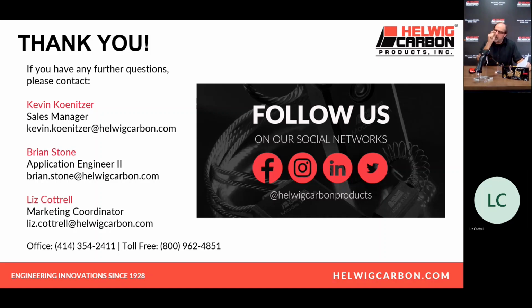Projected life. Even our smallest little kits for little motors that are tucked inside there, we're still talking minimum 5 years under 24/7 application. The things just last forever. Two things cause wear in a brush: electrical from arcing and mechanical just from physical wear. This is not a DC brush like you might think of that has to be replaced every so often. It has no electrical wear because, remember, we put a spring in a silver graphite brush and we maintain contact. So as soon as there's any voltage on the shaft, it's immediately dissipated before there's any arcing, so no electrical wear.